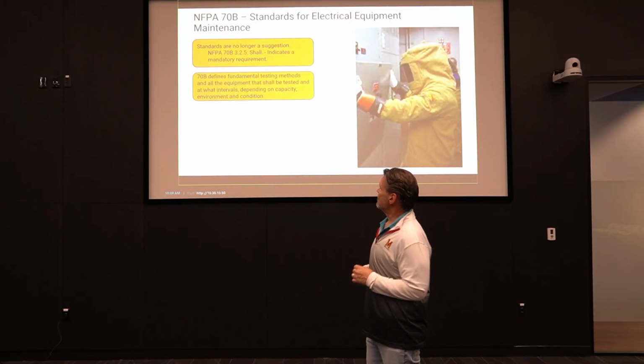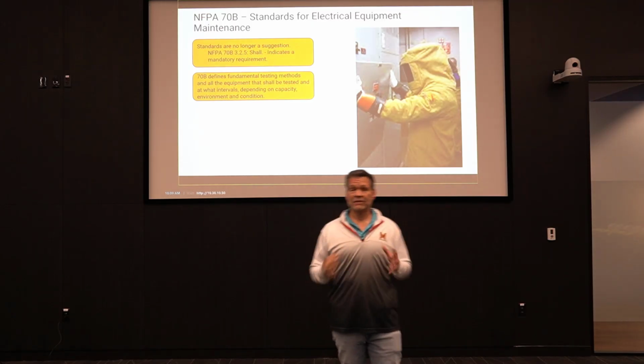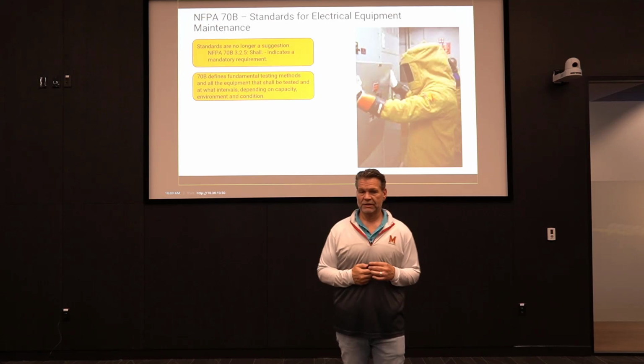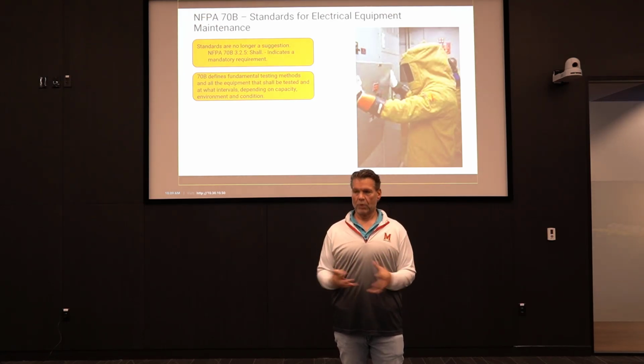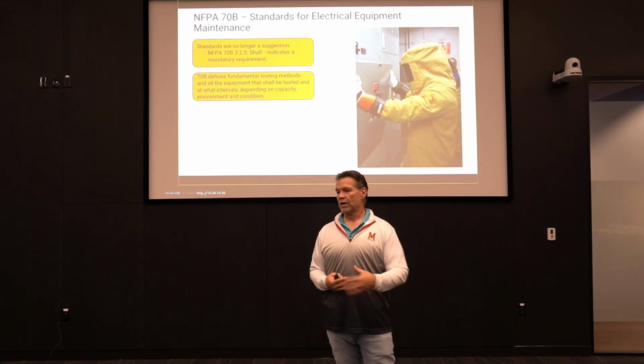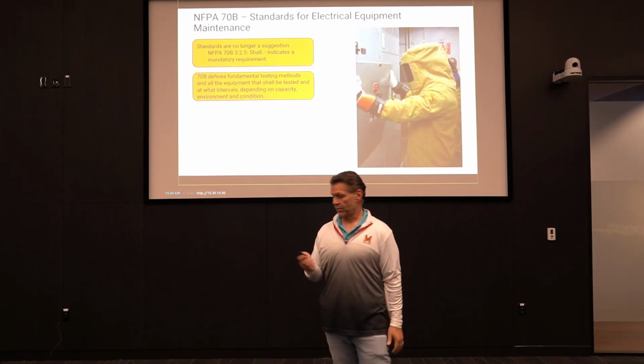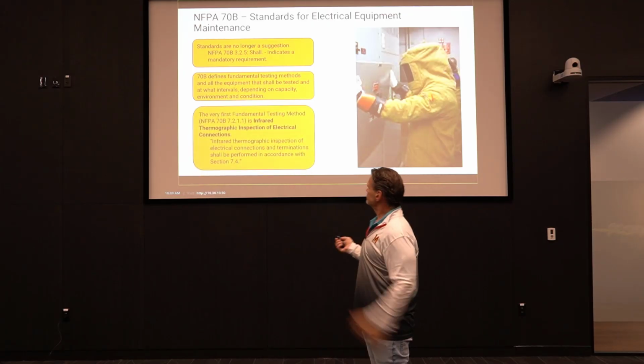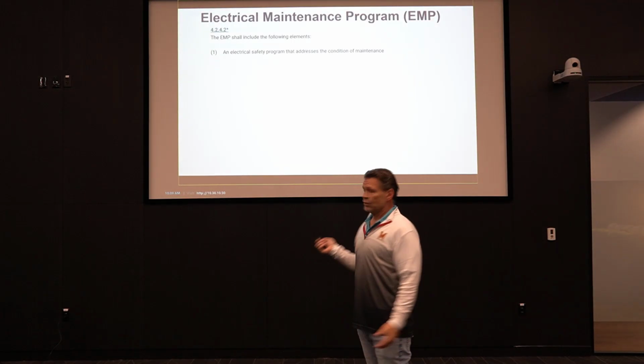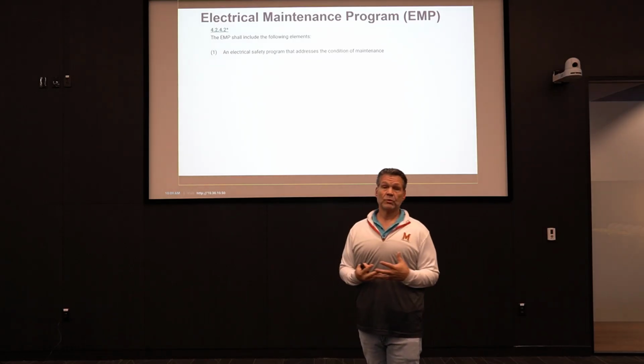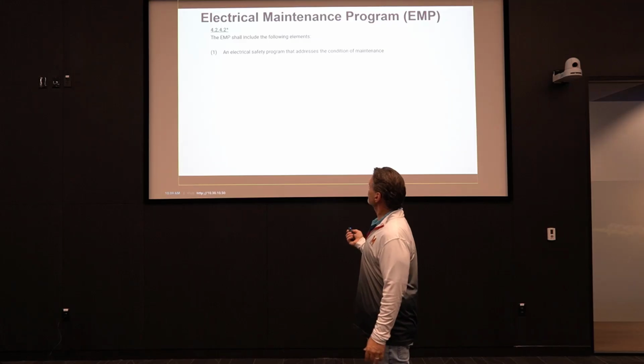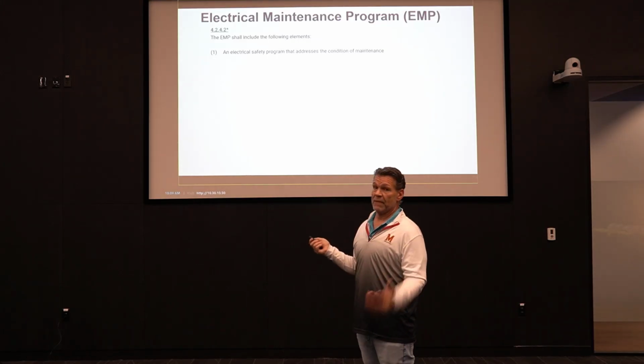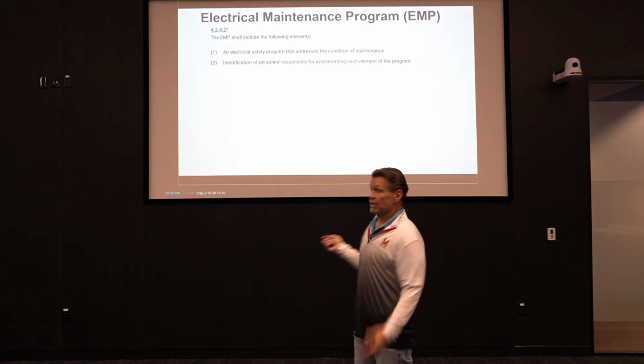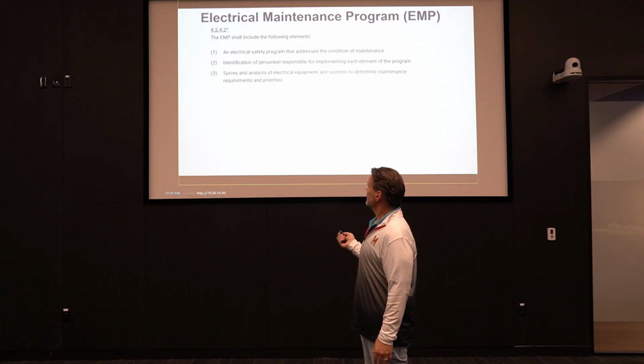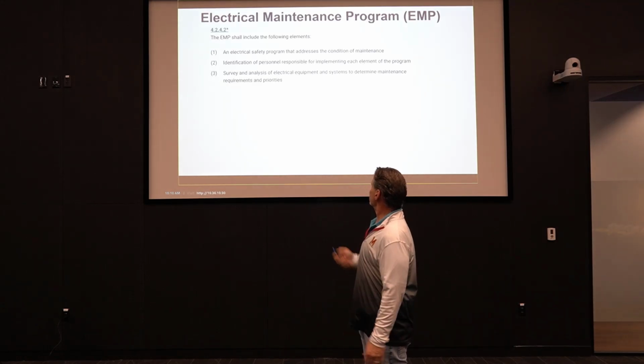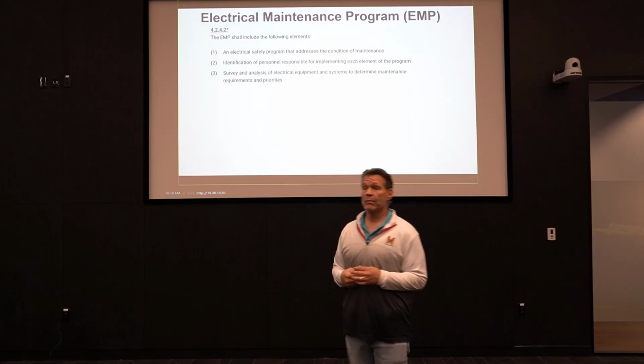It defines the fundamental testing methods and equipment that needs to be tested and at what intervals it needs to be done. So you need to have a written maintenance program, and you also have to have a person in charge of that program. So here are some of the elements that have to go into this program. It addresses the condition of maintenance of the equipment, identification of the person who is responsible, survey and analysis of all the equipment and the systems to determine their maintenance requirement and priorities.